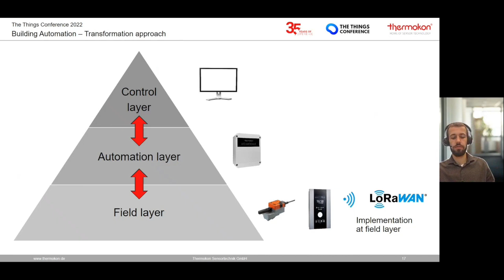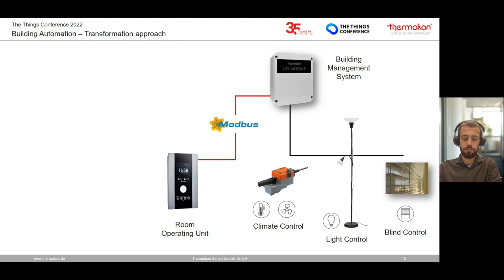Here you see a typical Modbus building management system. On the upper part you have the control and automation layer, connected to the different field devices. You have a room operating unit connected via a Modbus bus system directly, giving its inputs to the building management system. The building management system itself then controls the climate, heating, cooling, and ventilation actuators, controls the light, and controls the blind.